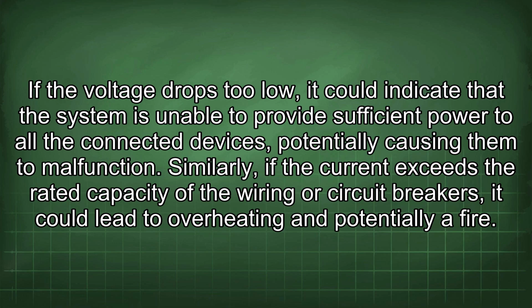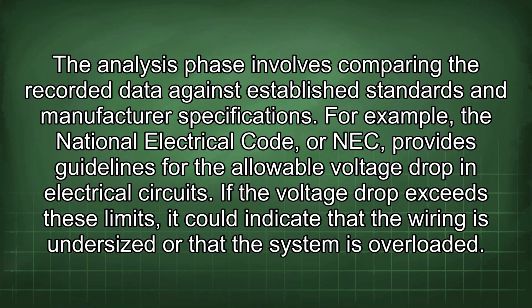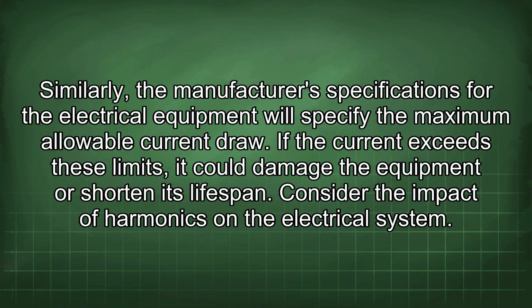Similarly, if the current exceeds the rated capacity of the wiring or circuit breakers, it could lead to overheating and potentially a fire. The analysis phase involves comparing the recorded data against established standards and manufacturer specifications. For example, the National Electrical Code, or NEC, provides guidelines for the allowable voltage drop in electrical circuits. If the voltage drop exceeds these limits, it could indicate that the wiring is undersized or that the system is overloaded. Similarly, the manufacturer's specifications for the electrical equipment will specify the maximum allowable current draw. If the current exceeds these limits, it could damage the equipment or shorten its lifespan.